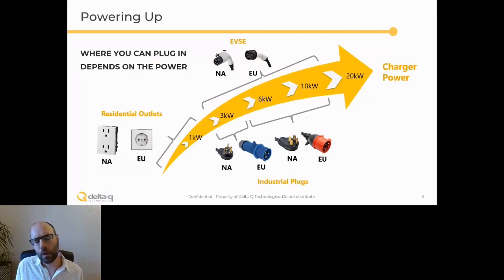Beyond that, when you get to 3, 6, 10, up to 20 kilowatts, you're talking about an industrial plug, single phase for lower powers, 3-phase for higher powers, or a charge station. The typical J1772 connector in North America is single phase, so typically 3 or 6, maybe 10 kilowatts from a 60 amp breaker. In Europe, the Type 2 connector is 3-phase power, so you can draw 10, maybe 20 kilowatts with a 20 or 40 amp 3-phase breaker. So the choice of power level starts to drive where you can plug in.